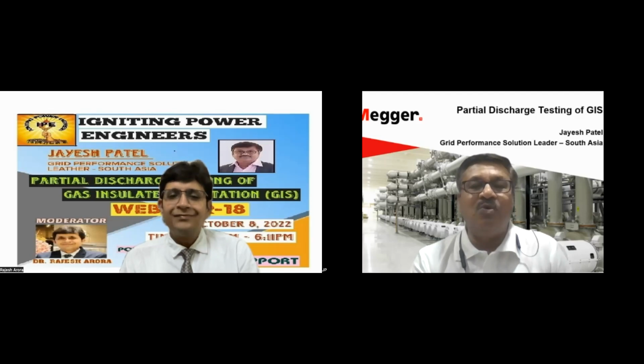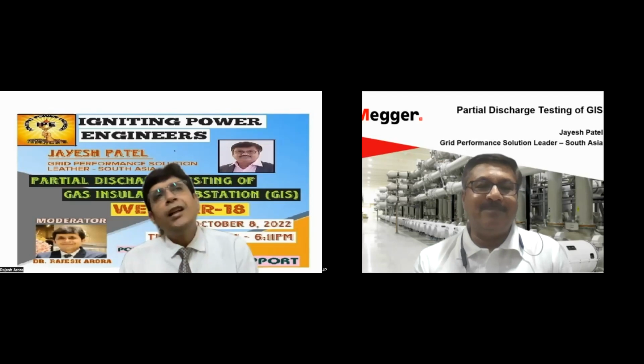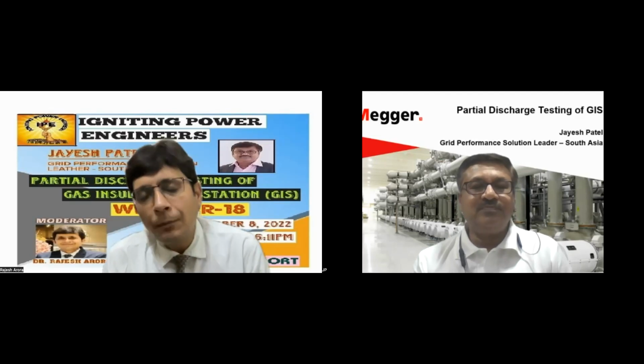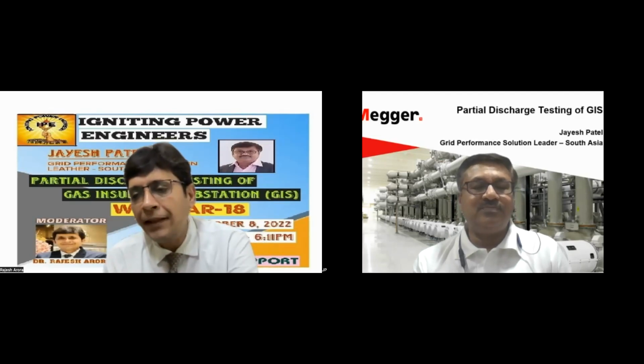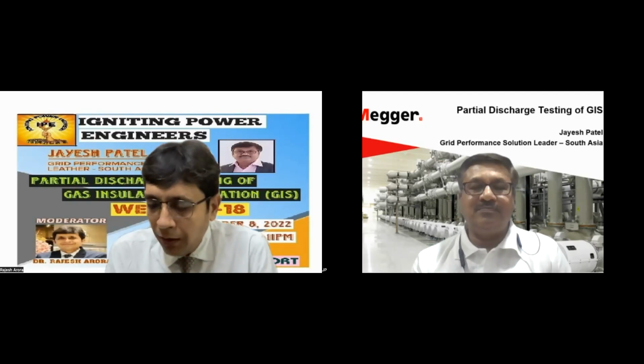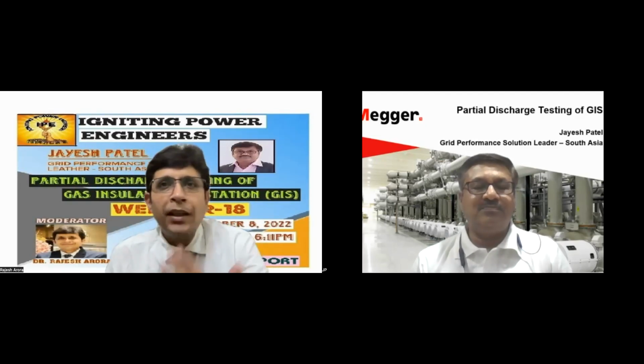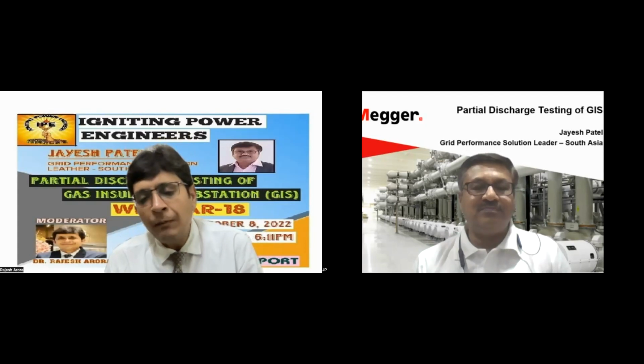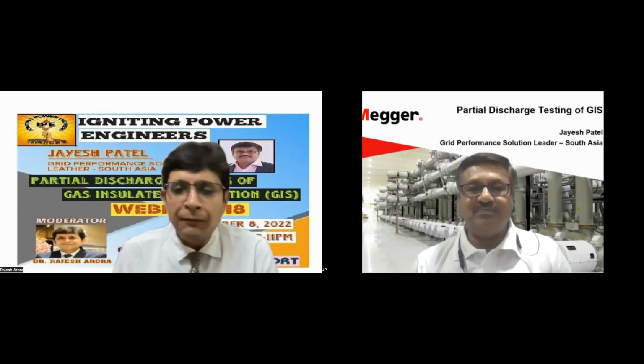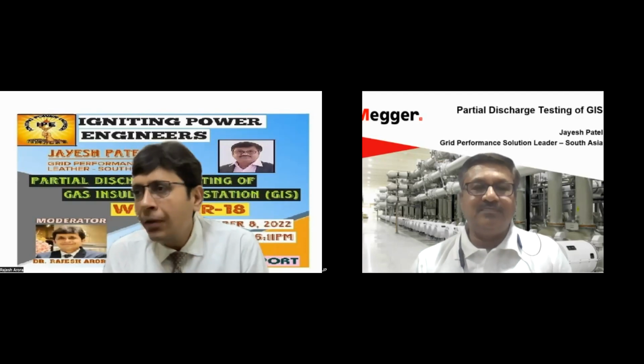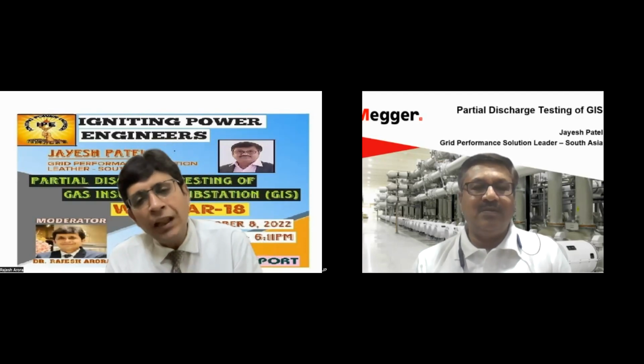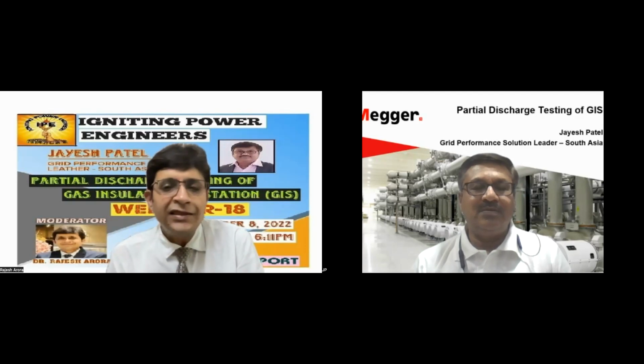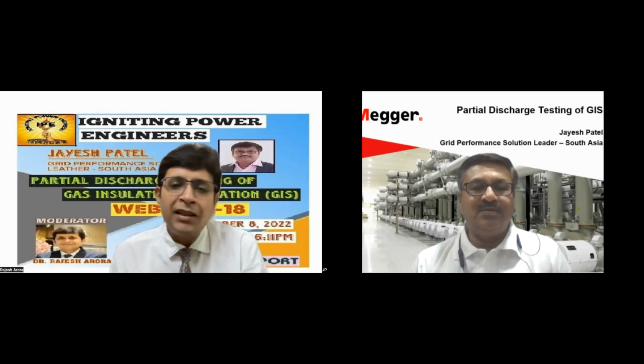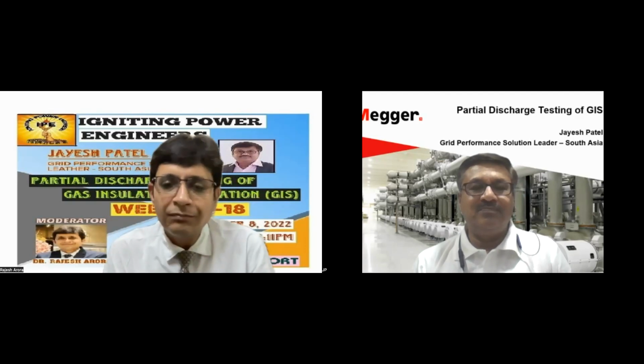So that's always some good part which is associated with partial discharge. Okay. And further, you elaborated about the portable, temporary, and the fixed continuous monitoring. You have explained that in the temporary monitoring systems, you have to use the same kit that will be working as a permanent for some time, for a day, for example. But do you think it will give the same results that we can expect from the permanent monitoring system?